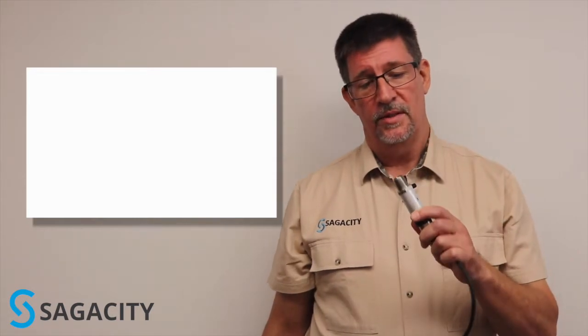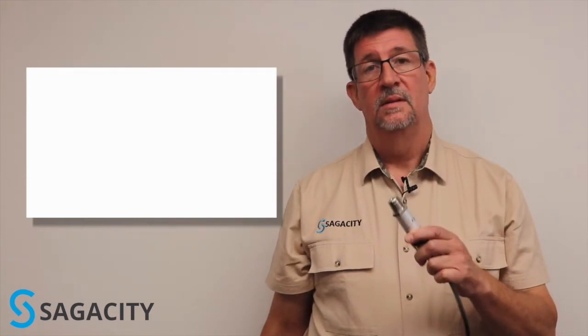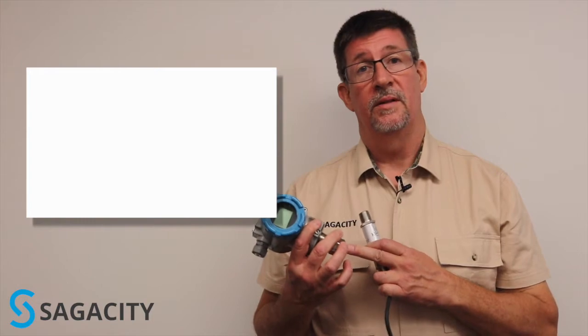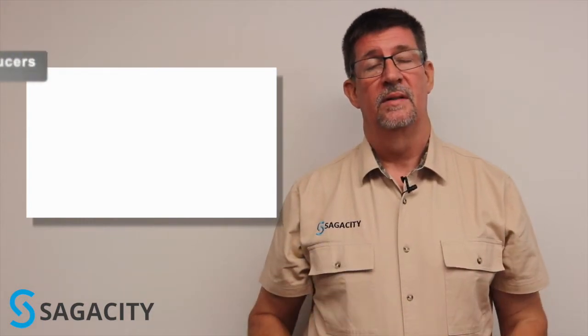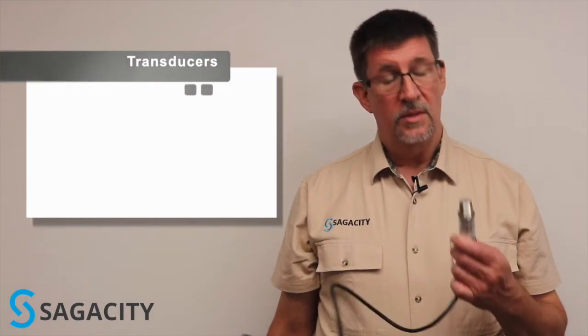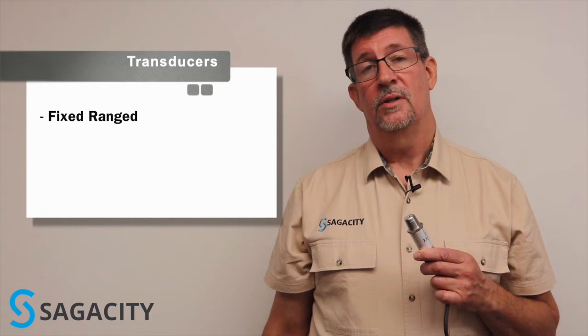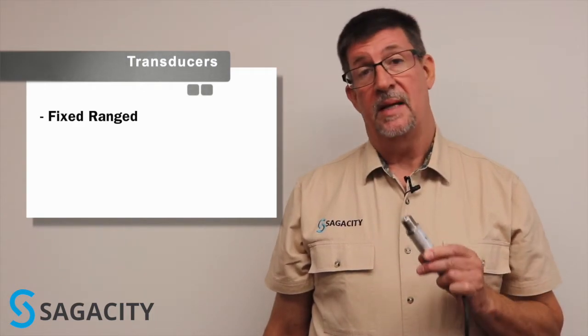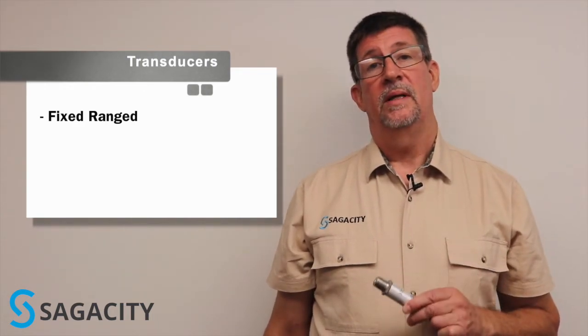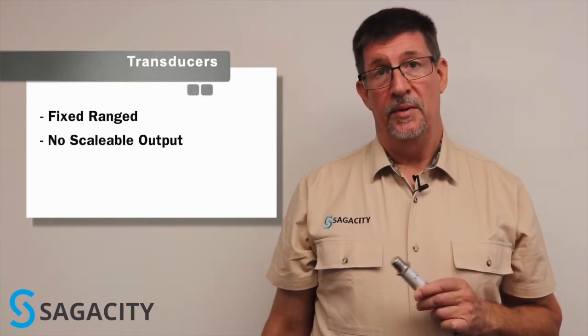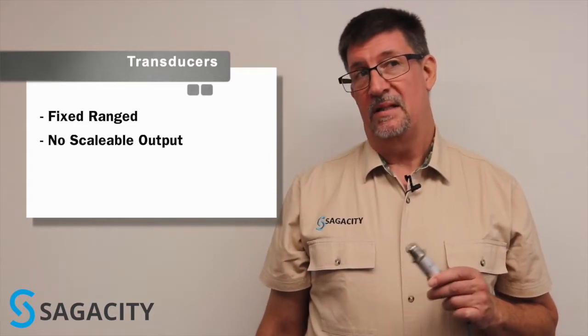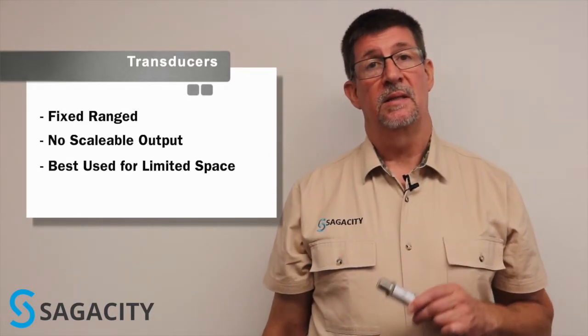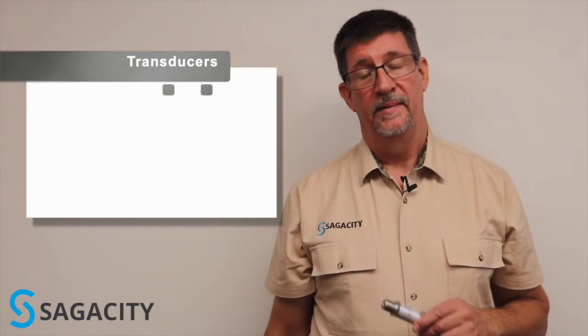Pressure transducers have a Wheatstone bridge, and a transducer is built into the transmitter, but they have differences. Transducers are typically a fixed range device, although like this one it's calibratable. It doesn't have a scalable output and is typically used in applications where space is limited and you don't need a display.